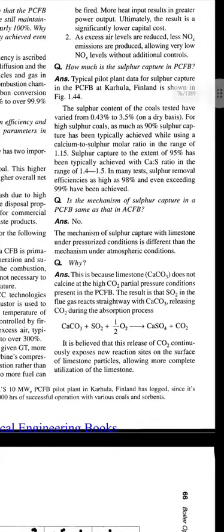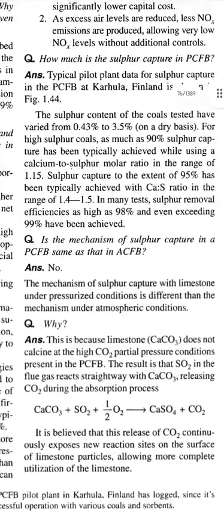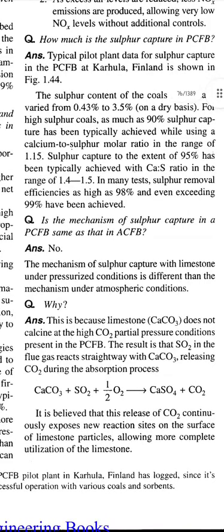Next question: How much is the sulfur capture in PCFB? Answer: Typical pilot plant data for sulfur capture in the PCFB at Karhula, Finland is shown in the figure. The sulfur content of the coals tested has varied from 0.43 to 3.5% on a dry basis.